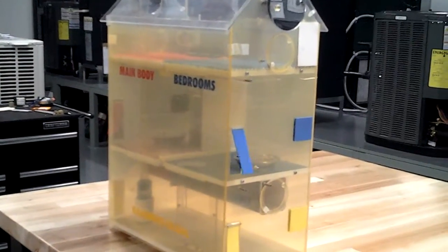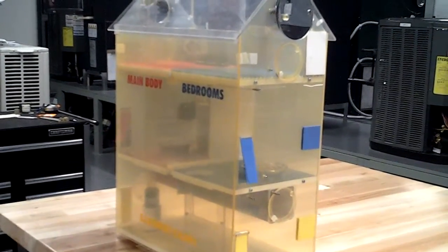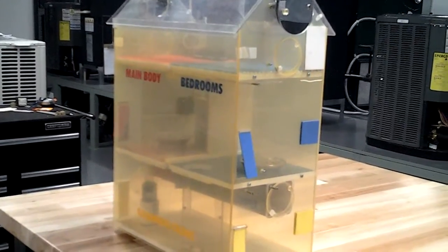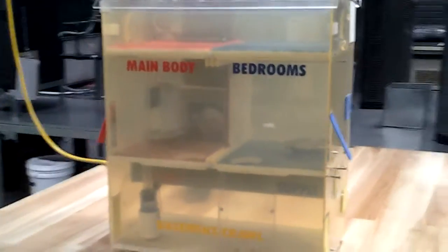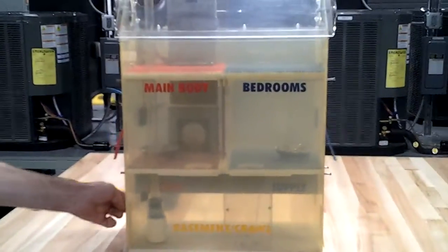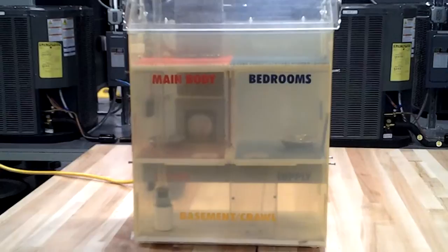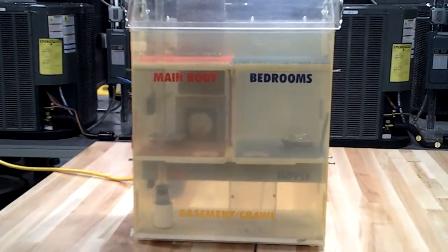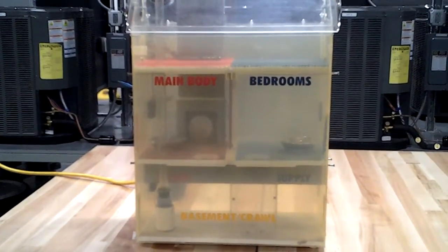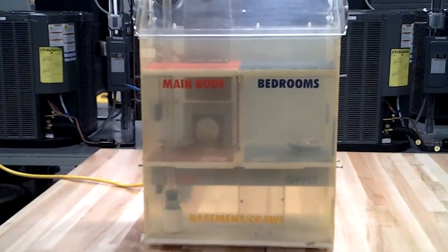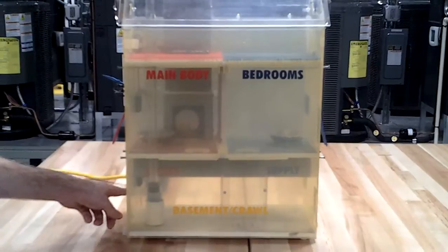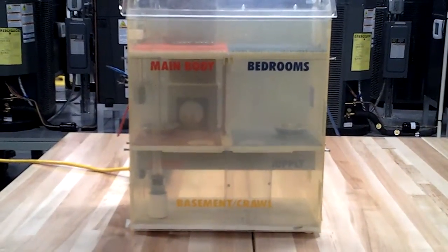Ideally, the net pressure within a building relative to the outdoors should range from slightly negative to neutral during the cold weather season in order to minimize exfiltration, as demonstrated here. Adversely, the net pressure within a building relative to the outdoors should be slightly positive during the warm weather season to minimize infiltration, as seen there.